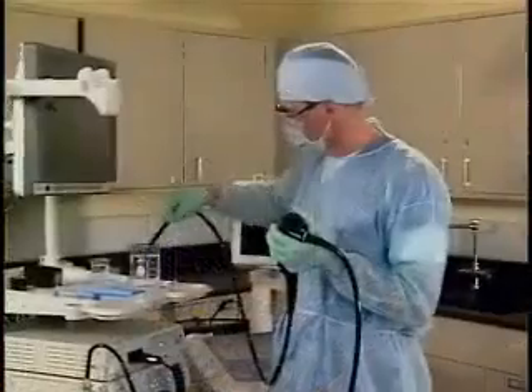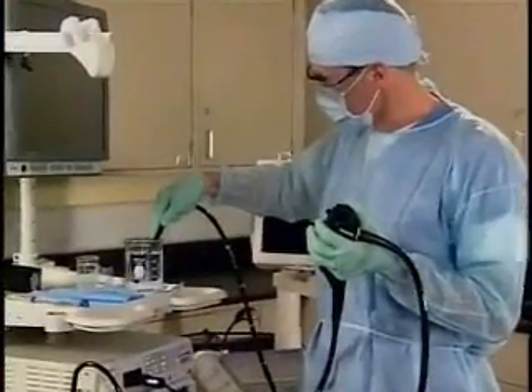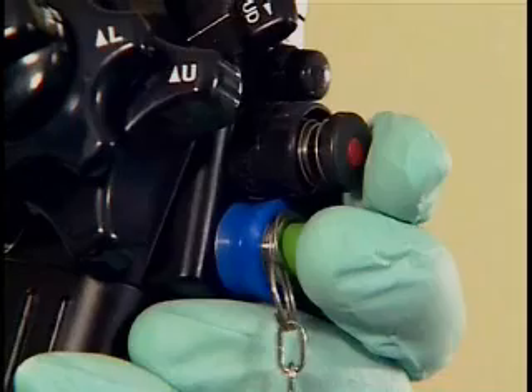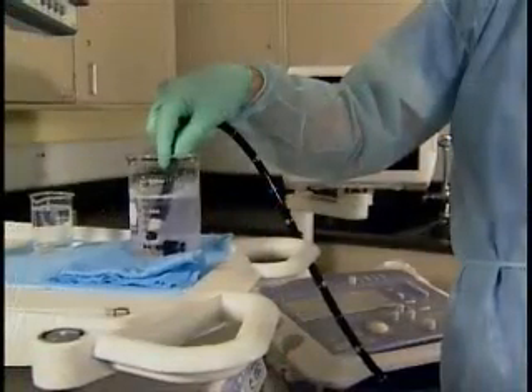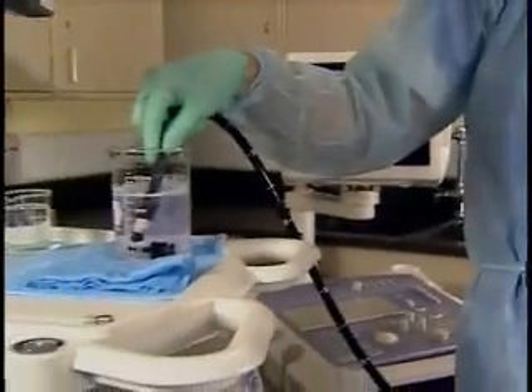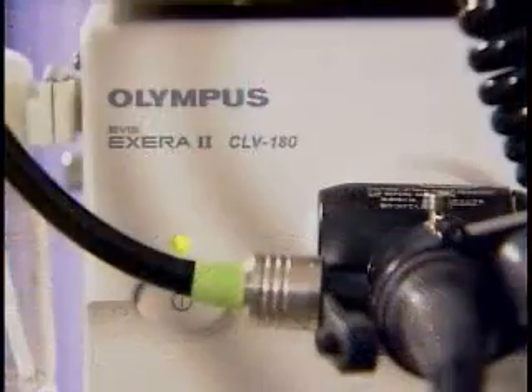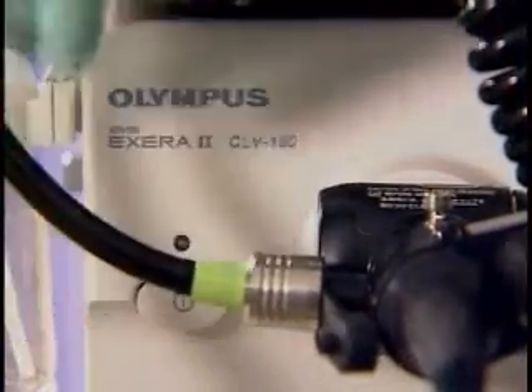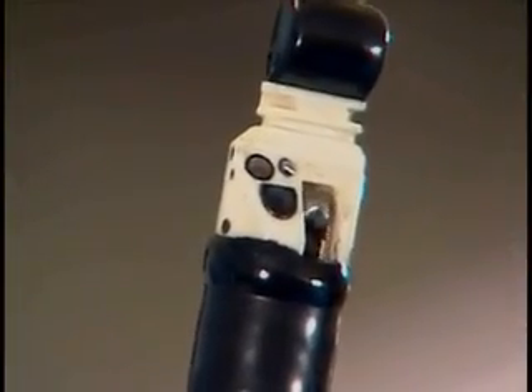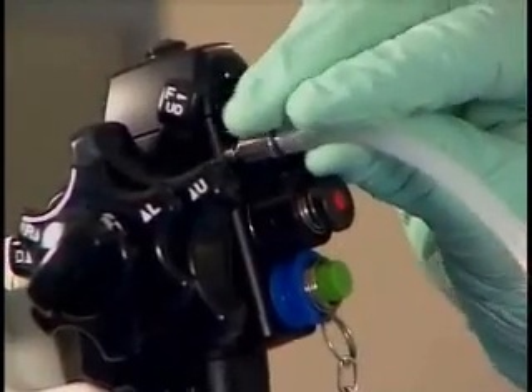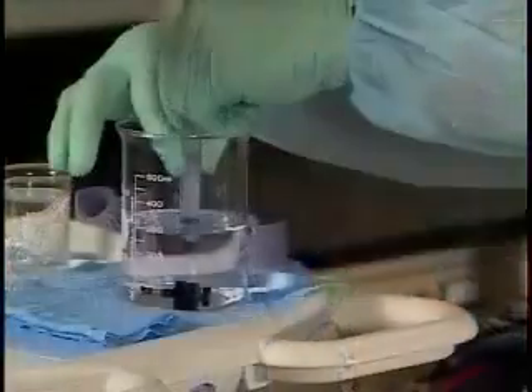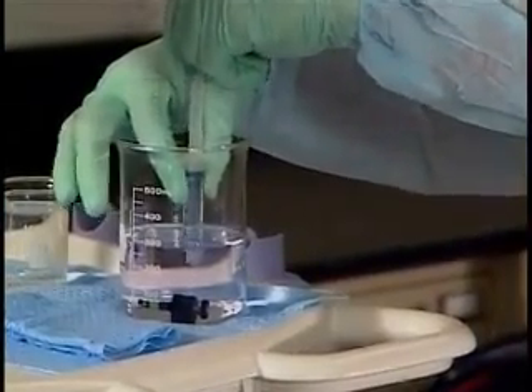Immerse the distal end of the endoscope in the detergent container. Depress the air-water channel cleaning adapter valve and feed water for 30 seconds. Release the adapter to feed air through the air-water channels for 10 seconds. Turn off the light source. If you are reprocessing an ultrasound endoscope with an elevator, connect the washing tube to the elevator wire channel inlet. Fill a 5 cc syringe with detergent solution and flush the channel several times.